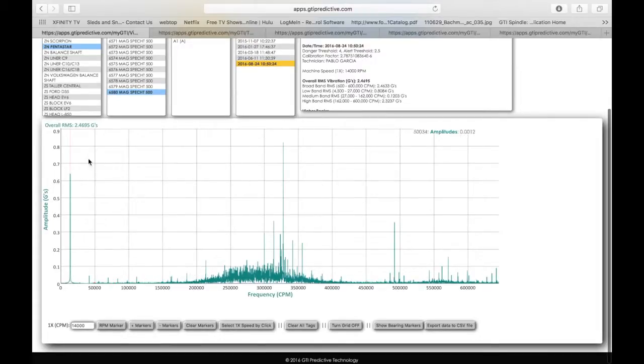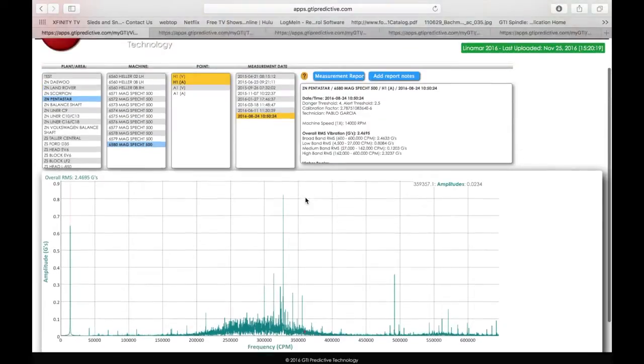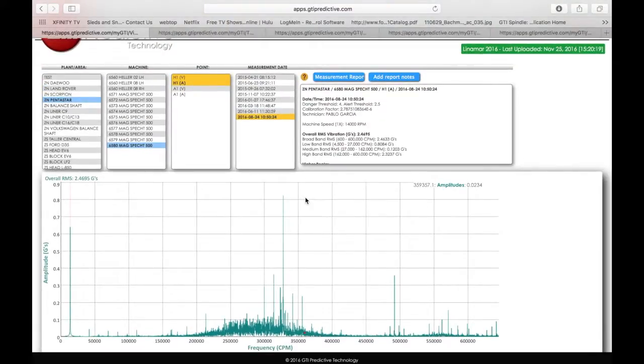But we're only at 2.4 g's and we have a large peak at running speed, which is probably an imbalance that is causing this bearing defect to start rapidly degrading over time.